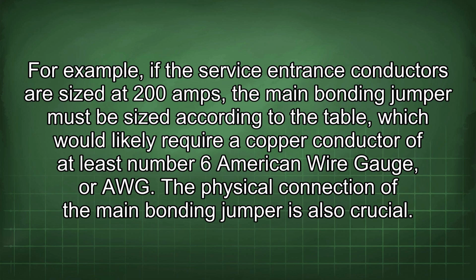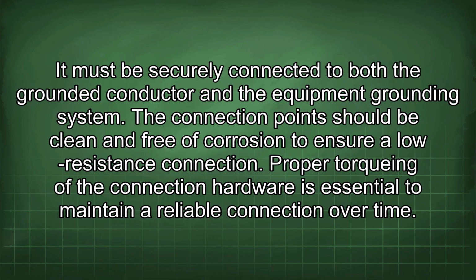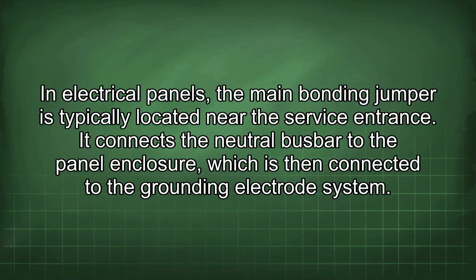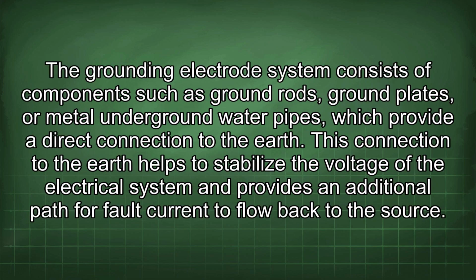The physical connection of the main bonding jumper is also crucial. It must be securely connected to both the grounded conductor and the equipment grounding system. The connection points should be clean and free of corrosion to ensure a low resistance connection. Proper torquing of the connection hardware is essential to maintain a reliable connection over time. In electrical panels, the main bonding jumper is typically located near the service entrance. It connects the neutral busbar to the panel enclosure, which is then connected to the grounding electrode system. The grounding electrode system consists of components such as ground rods, ground plates, or metal underground water pipes, which provide a direct connection to the earth.